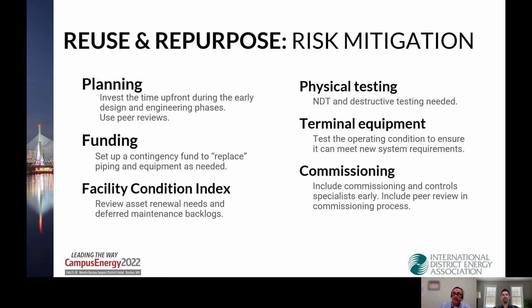Terminal equipment: we wanted to test all those air handlers where we changed out steam coils with face and bypass over to some kind of glycol coils. We took some preliminary balancing measurements to see where we were as far as the pressure drop, looked at the pressure drop expected for the new coils, and made sure that the fans had the capacity. And pretty much in all cases, because they were mostly face and bypass, we actually decreased the pressure drop across the coils in these air handlers. And then finally, commissioning.